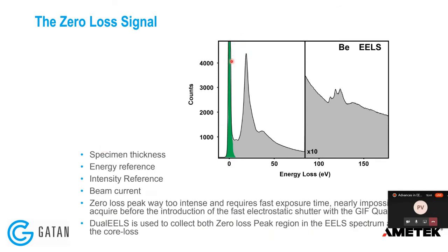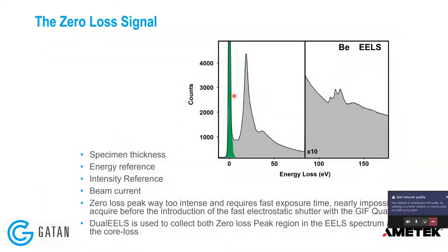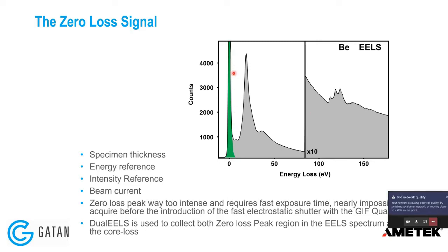The zero loss peak is very intense. Even though it may seem unimportant, you can extract information about specimen thickness and use it as an energy reference — for example, to measure the chemical shift of your material. You can also calibrate your camera based on zero loss peak intensity and extract information about beam current. The dual EELS capability developed with the Quantum gives you the ability to collect the zero loss peak as well as all other regions of the EELS spectrum under the same conditions.